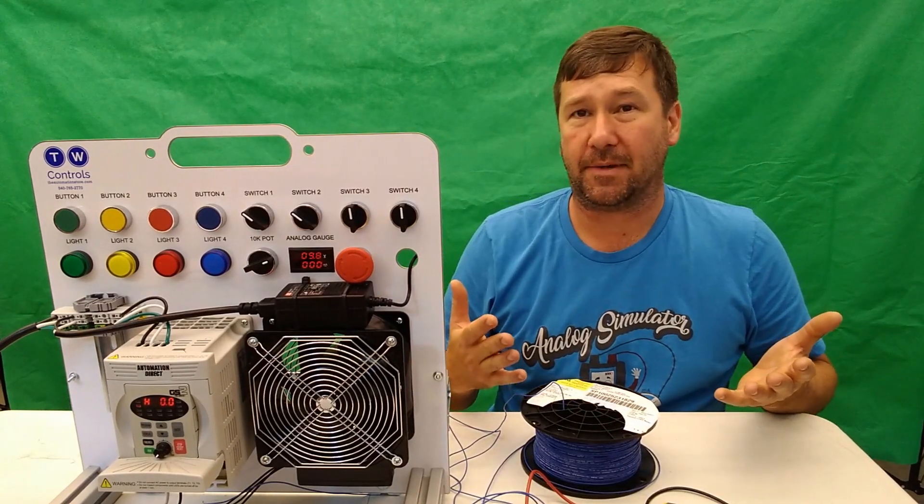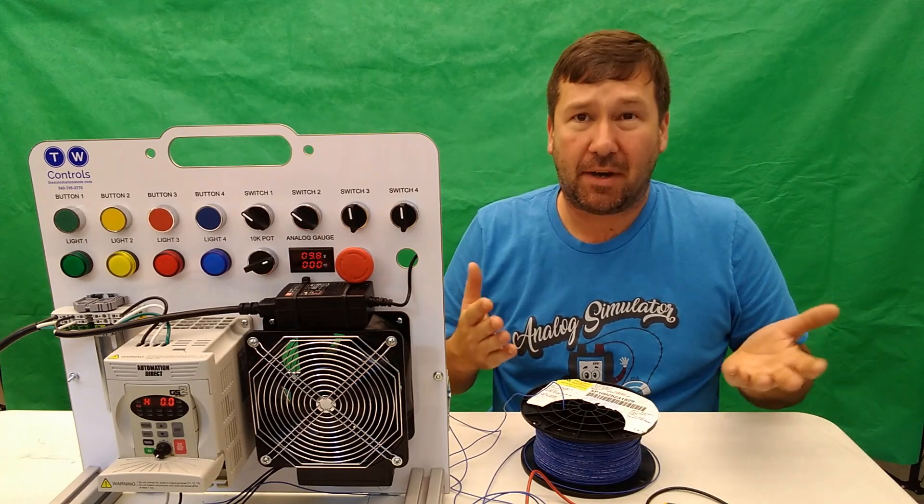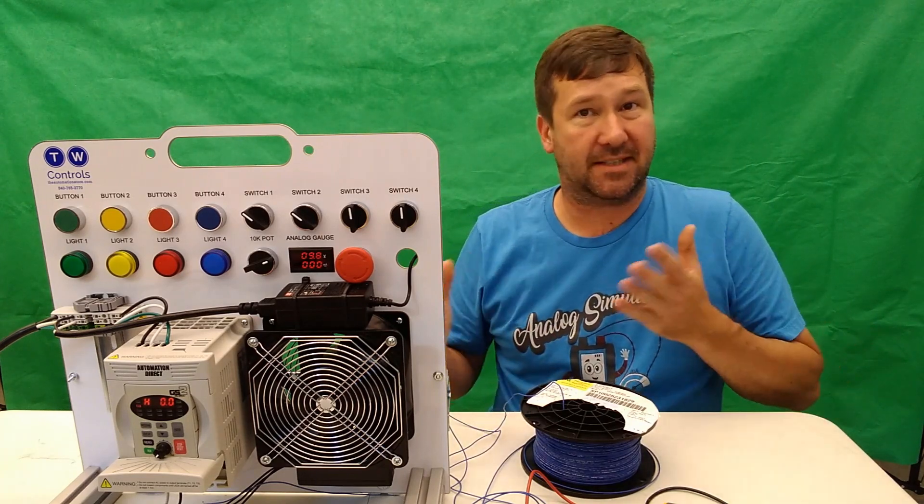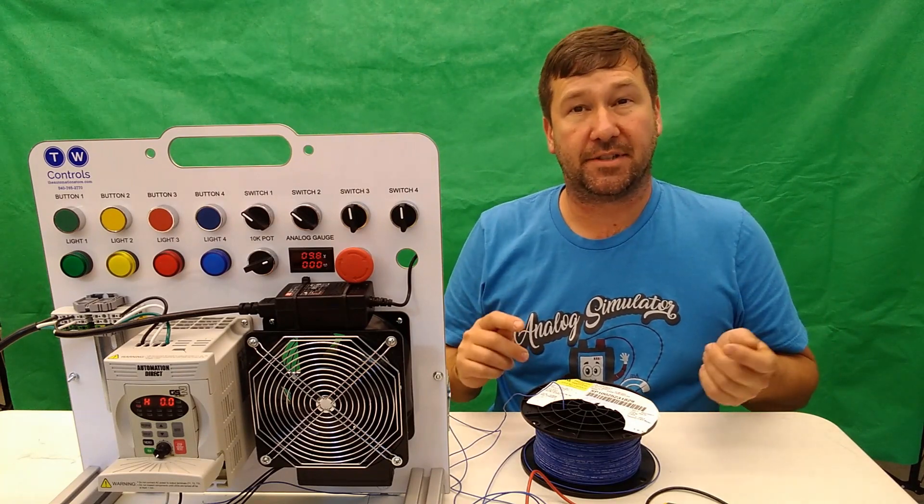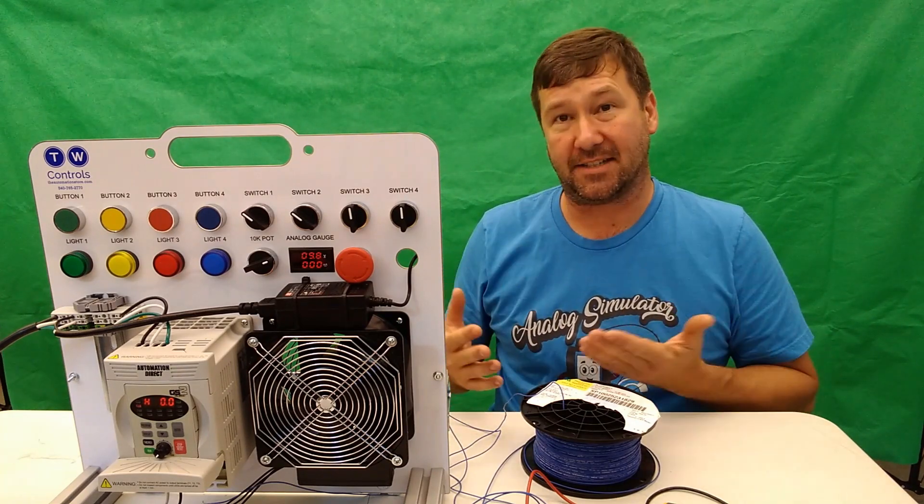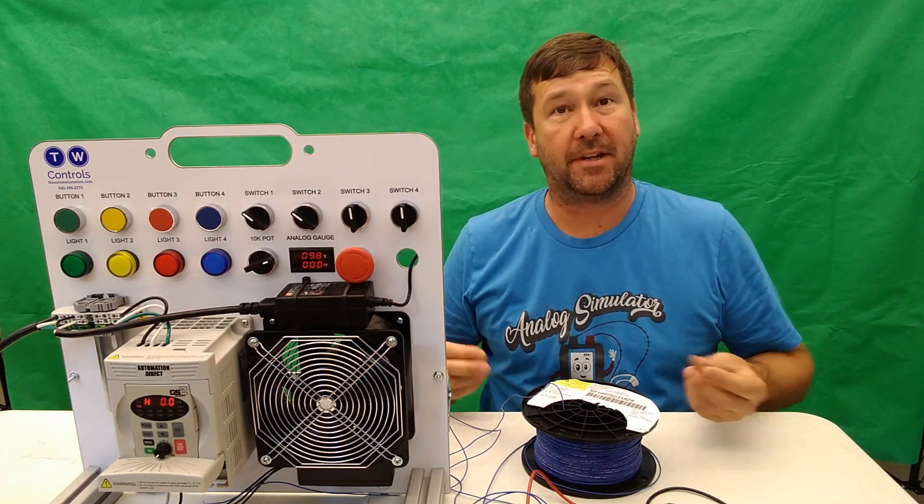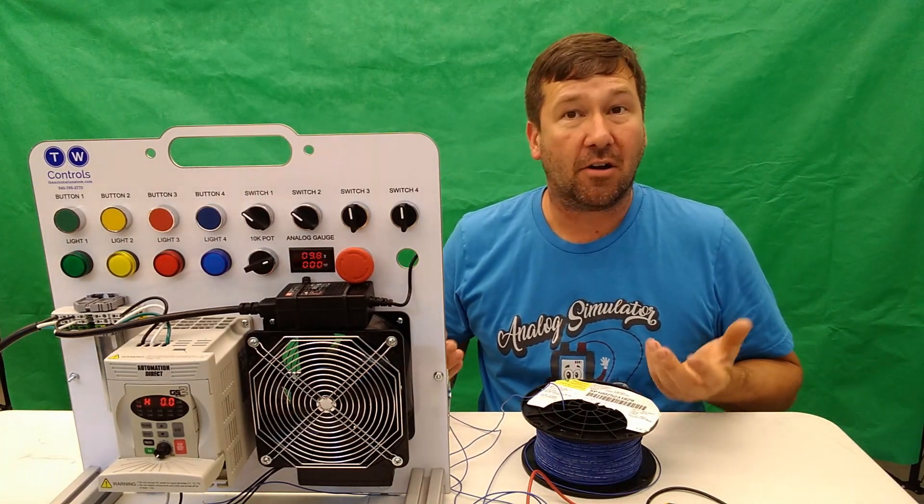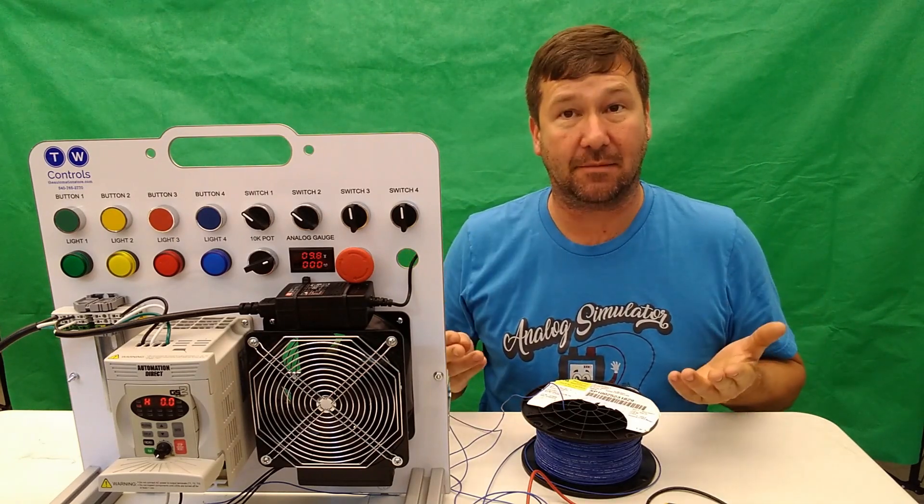Now in a control cabinet where components are really close together, this isn't much of an issue. And that's why you'll see drive speed commands and various internal components be voltage signals. But you'll almost never see a voltage signal actually exit a control cabinet. For signals exiting the control cabinet, where the distance can be longer and the environment can be more harsh, we need a different type of measurement, and that's going to be amps.